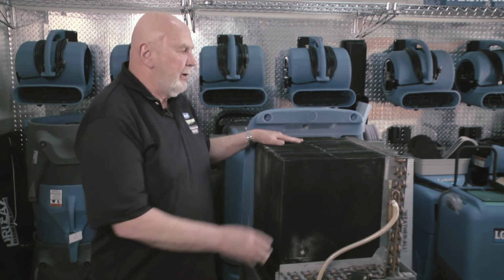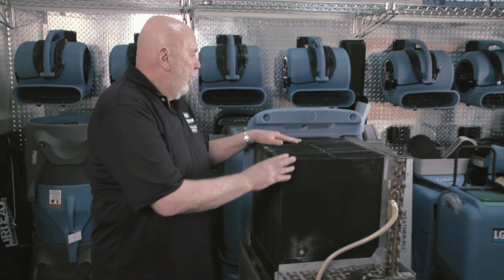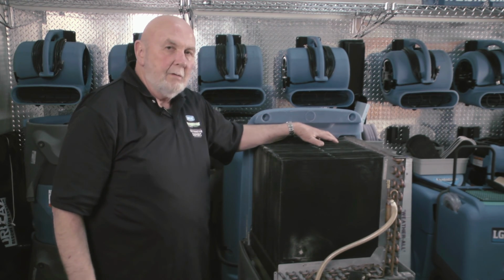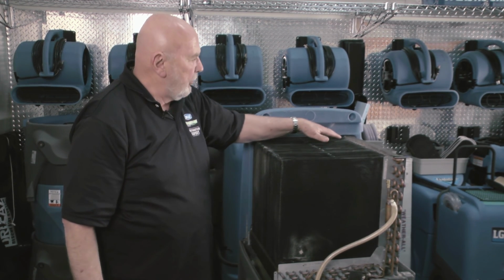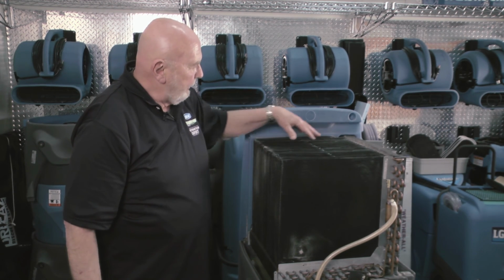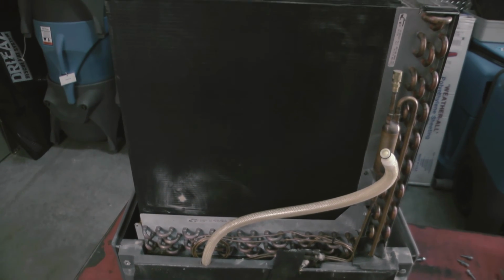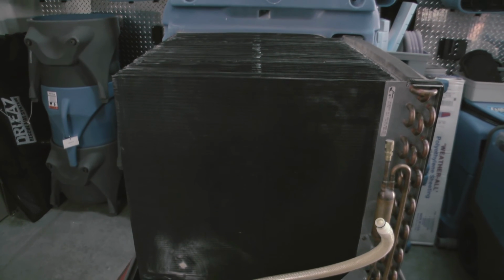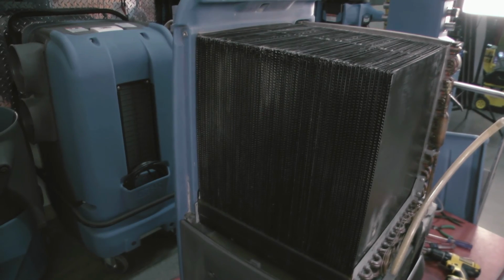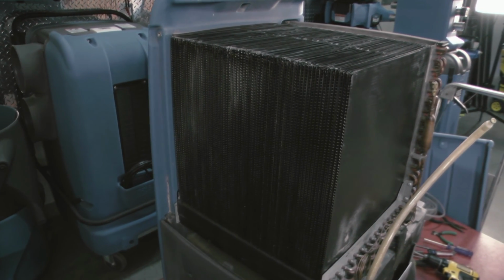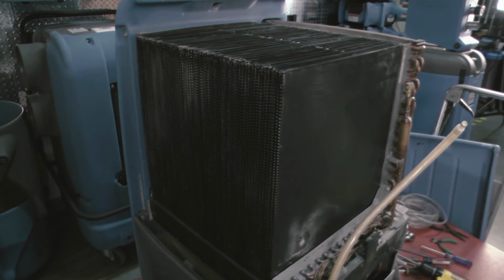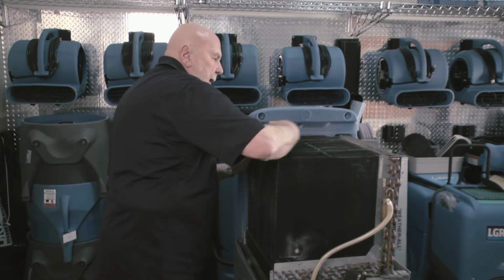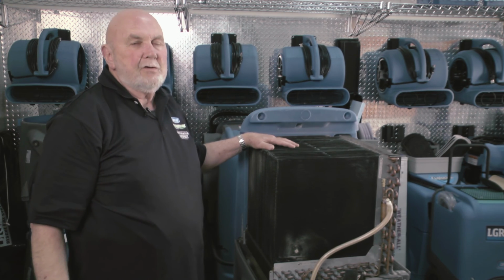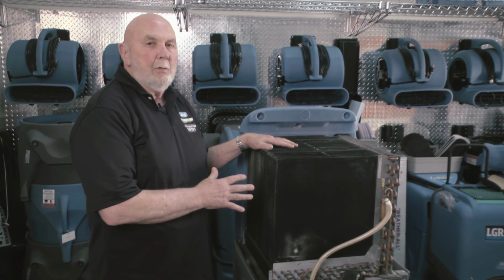When the heat block is really dirty, I use a light solution of dishwashing soap, spray it on, and use water—not with a nozzle, just the outlet on the hose—to wash it down in there. Then I take the hose and hold it above the heat exchanger and wash it down numerous times, making sure I get all of the soap out of the unit.